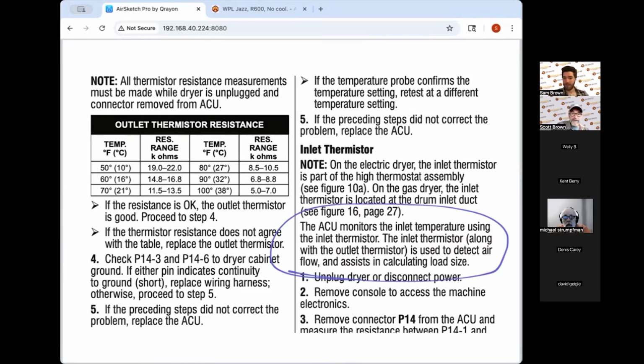By the way, this illustrates two good reasons to just scan the dummy directions. We don't scan them for procedures and look at what do I check now? We're looking for two things. Did they bury specs in here? Oh, yes, they did. They buried the outlet thermistor spec. And do they have tidbits on the algorithm that may affect my troubleshooting? Yes, they did. So that's what they did in this case. How did I know to do that? Because it was like, well, there's no place else to look. And I knew what I was looking for.